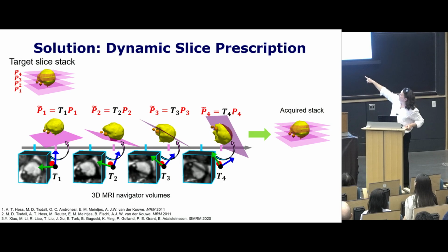Now, you see there are black streaks through the volumes. That's real, and it's called spin history artifact. What happens is that when you excite the slice in MR terms to acquire it, the spins flip, and then you watch their relaxation to the steady state. And it turns out they take a long time. So what you're seeing as black streaks is the previous slices. It's a shadow of the previous high energy slice in these volumes.